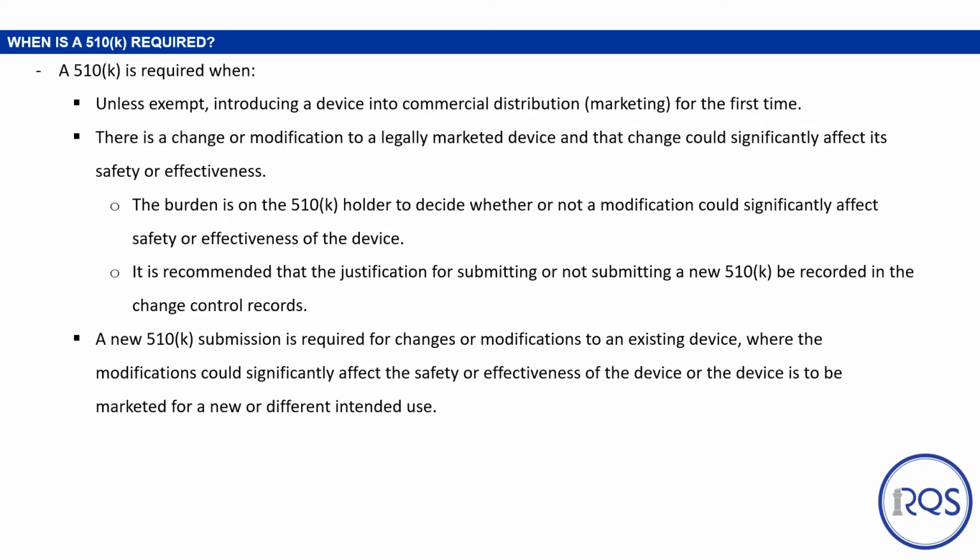And lastly, a new 510K submission is required for changes or modifications to an existing device where the modifications could significantly affect the safety or effectiveness, or if the marketed device is intended to be used in a new or different way.